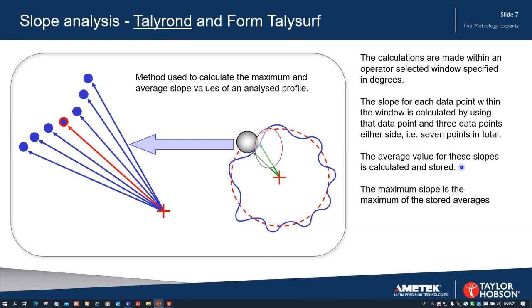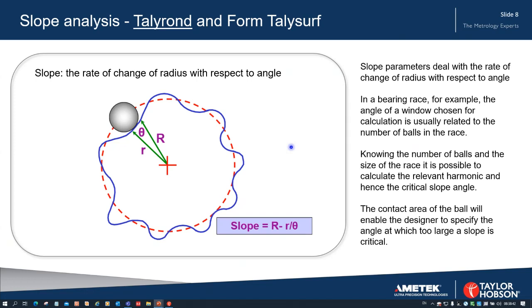The average slope is the average of all the stored average slopes. The units are microns radially per degree as we go around the part, so we're dealing in microns per degree for slope values. Slope is the rate of change of radius with respect to angle.